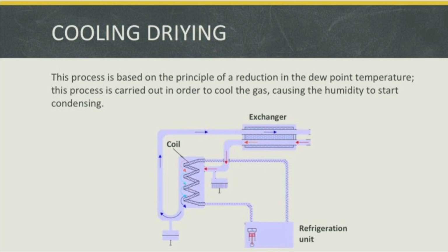Number 1. Compressed air enters the dryer by first passing through the air-air exchanger. Number 2. The hot air entering the dryer is cooled by dry, cold air from the heat exchanger vaporizer. Number 3. The water condensate is evacuated from the heat exchanger through the separator.